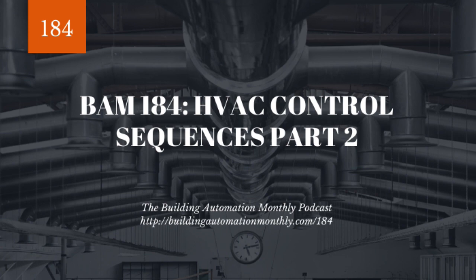All right. And we also tend to have a discharge air temp. Sometimes we will have some safeties in the form of static safeties, as well as low temperature safeties. There you have it. Those are all the points we have. So let's talk about the sequencing. Pretty much exactly the same as a fan coil, right? The fan might run all the time during occupied. It might only cycle on when we're in a heating or cooling mode.